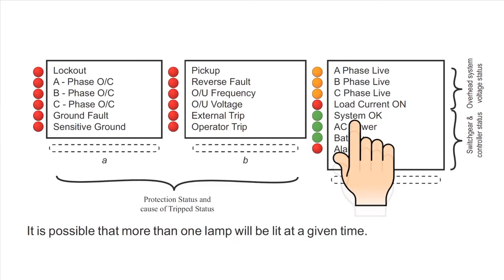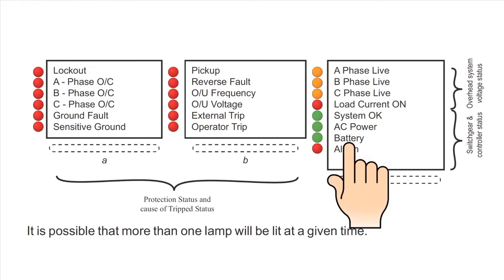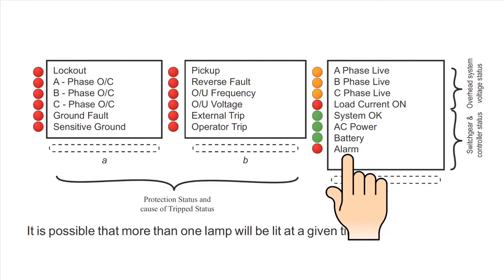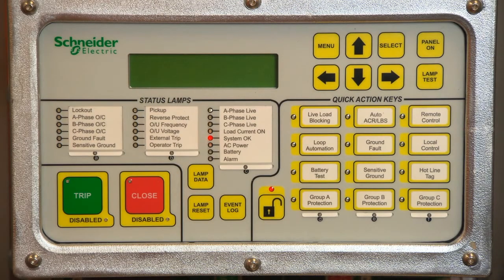Consult the event log. AC power. This LED is green when the AC source is OK and flashes red when it is not. Battery. This LED is normally green if the battery is on and in good condition. It will flash red if the battery is off or if it has failed a battery self-test routine. Alarm. This is a flashing red lamp when the trip or close circuits are isolated, the contact life is low, or the switchgear is locked. The quick action buttons or keys.